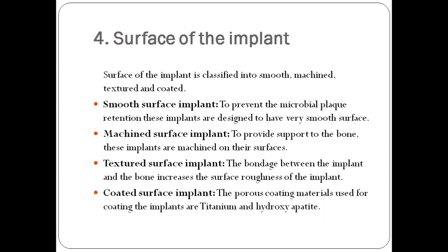The surface of the implant is classified into smooth, machined, textured, and coated. Smooth surface implants are designed to prevent microbial plaque retention. Machined surface implants provide support to the bone. Textured surface implants increase surface roughness to improve bondage between the implant and bone. Coated surface implants use porous coatings; the materials used for coating are titanium and hydroxyapatite.